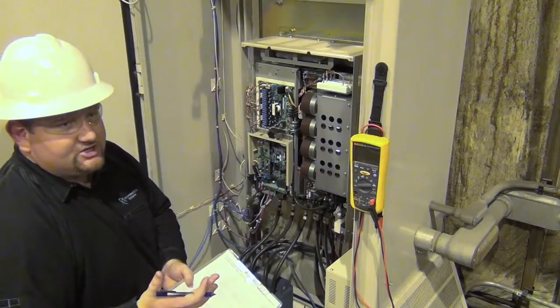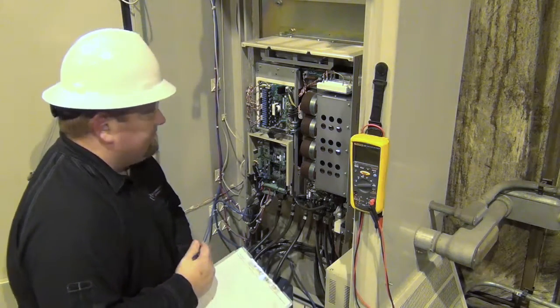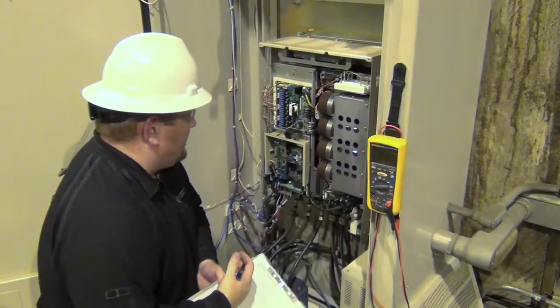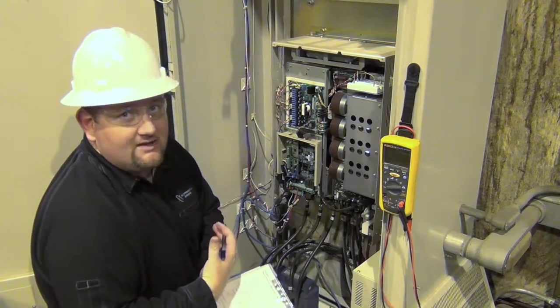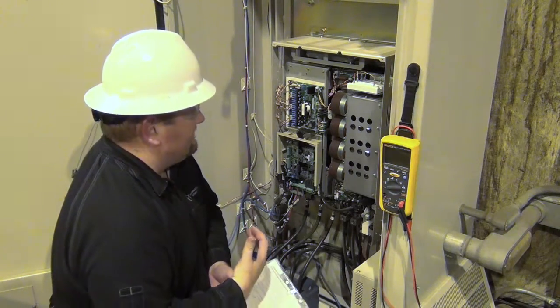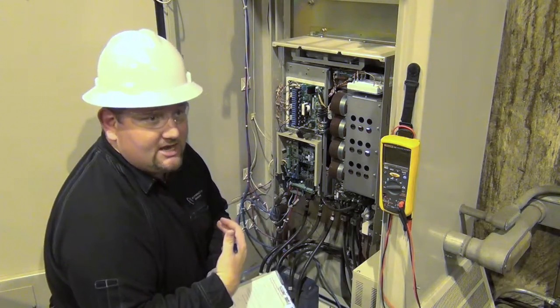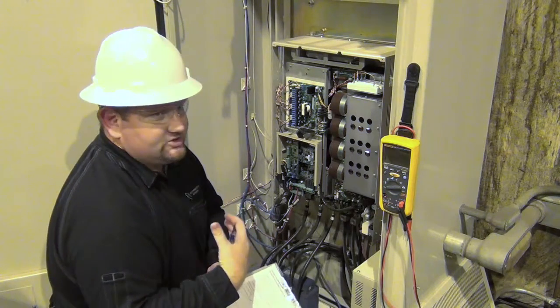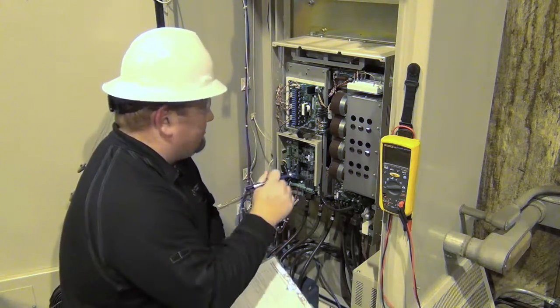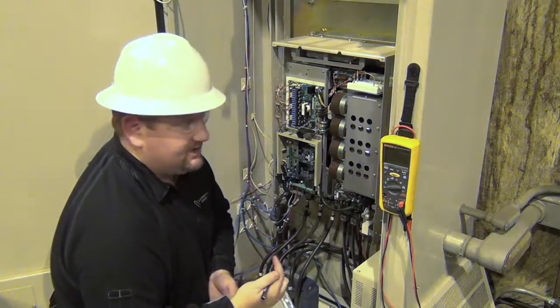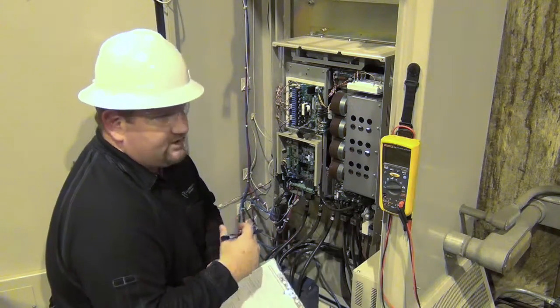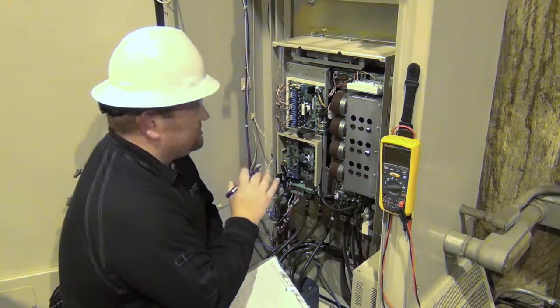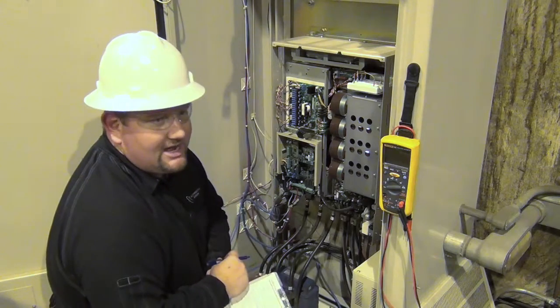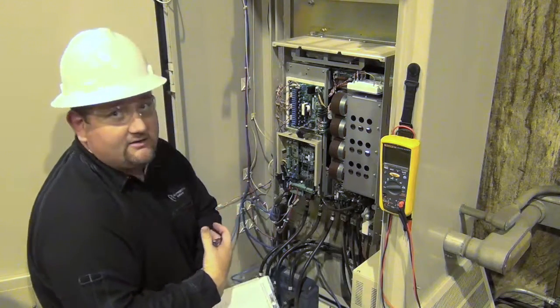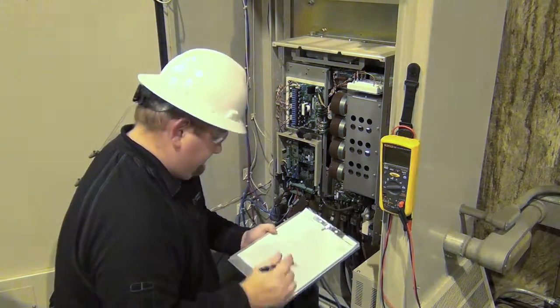This is one of those sections of performing maintenance where you have to decide what the value of continuing to disassemble the drive is versus the risk of actually damaging a component during that time, or introducing some new failure by not having a board seated properly or a connector seated properly. So it's our feeling, visually inspect what you can, see as much as you can, but we don't advocate actually disassembling the drive during routine maintenance.